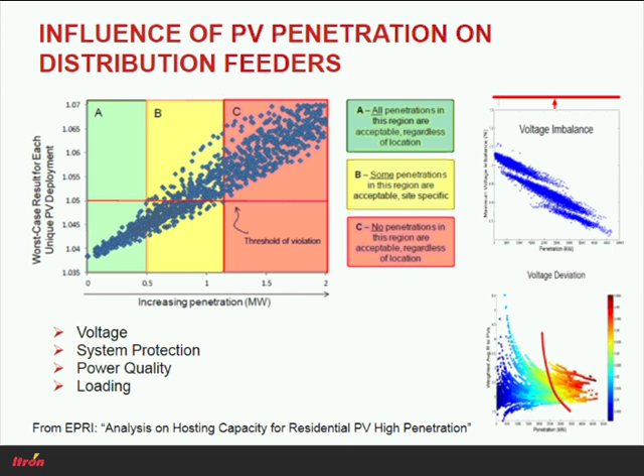So I mentioned that PV was intermittent. The other thing to remember about PV systems is that when cloud cover comes over the PV system, whether it's a large utility scale system or a large number of small scale residential systems, you're going to have a decrease in power output from the PV system. This can be rapid, it can be of short duration or long duration. But as clouds pass overhead, PV generation output is going to drop. And remember earlier I mentioned that PV actually masks load at each of the sites, residential or commercial rooftops, because to the utility it looks like that demand has dropped. When the cloud cover comes overhead, all of a sudden that load shows up because the PV generation drops and the load may still be the same, so now the apparent load increases. For sites that are under automatic demand response control, this can have some very interesting consequences.